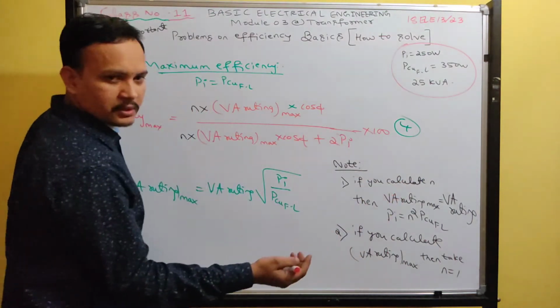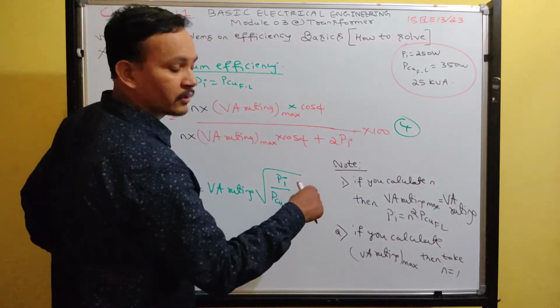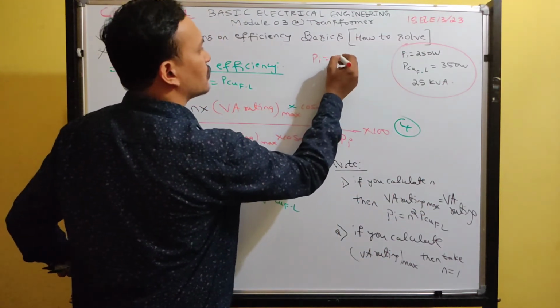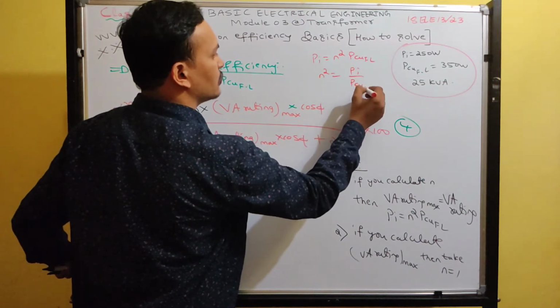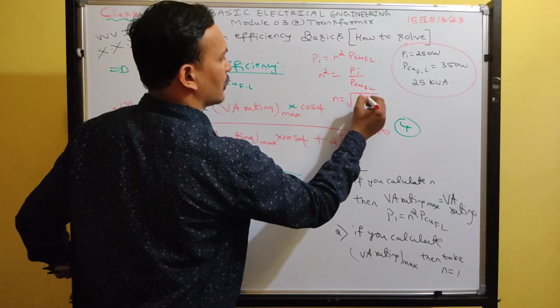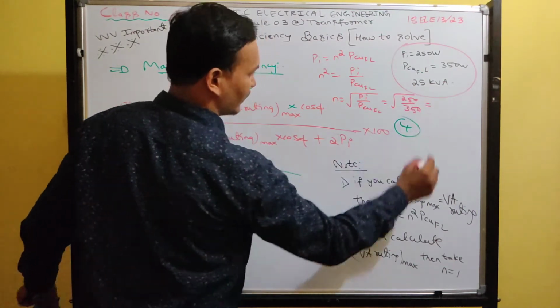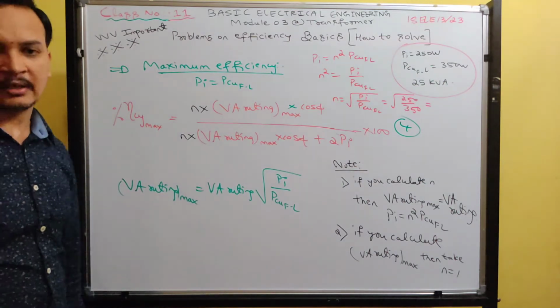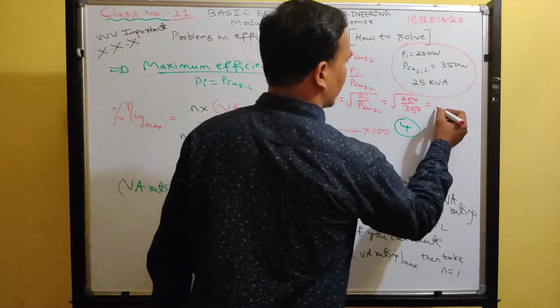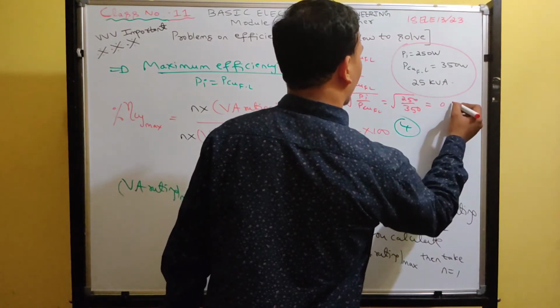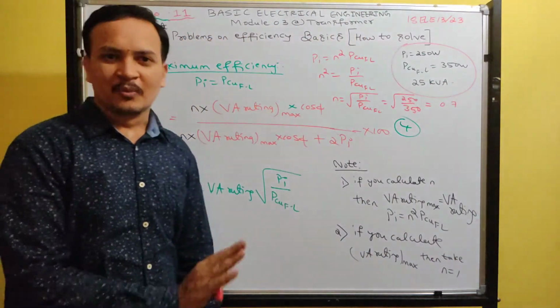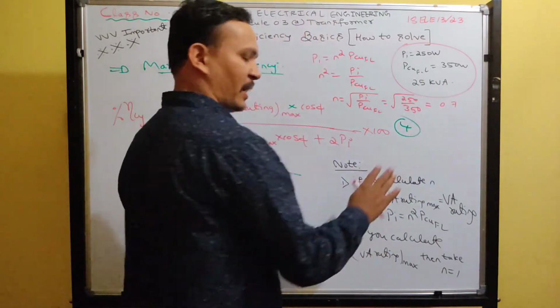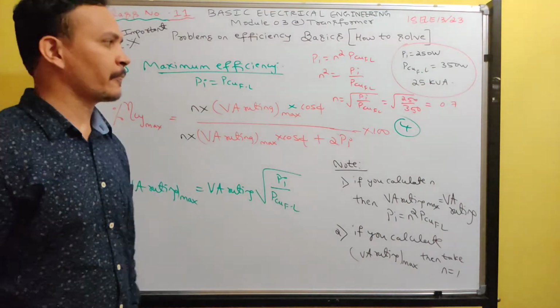First I am going to use this logic. If you calculate n, Pi is equal to n square PCU full load. Now what is n square? Pi by PCU full load. What is n value? Square root of Pi by PCU full load, square root of 250 by 350. So how much will you get for n? You won't get more than 1, that is sure. Some value you will get, let's say 0.7, but 0.7 is not correct. I will write some value, but that is less than 1.